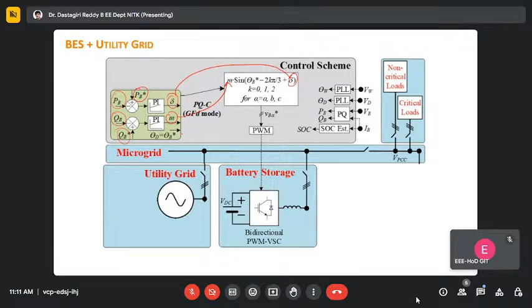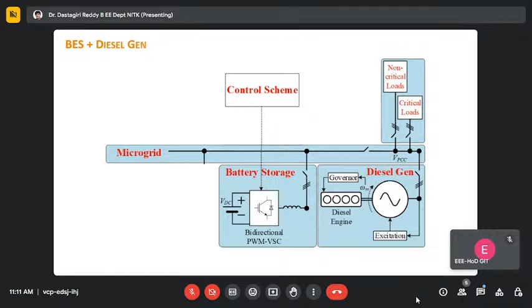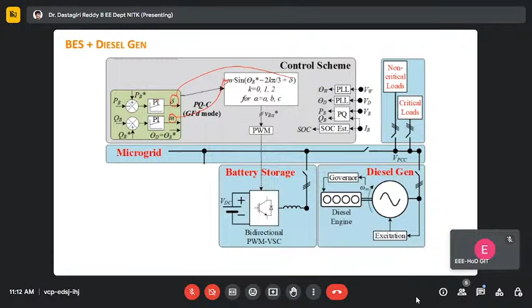So initially, what was there? Only one closed loop control, because there was only one source. Now the grid comes into picture, so I change the mode. My mode is now delta - I won't decide it myself, it will be decided by the PI controller. And the modulation index I won't decide either, it's decided by the Q control, that is reactive power control. Now if the diesel generator comes into picture, what will I do? I'll do the same thing, because the diesel will act as a strong grid and my control strategy will be the same - I update delta and update the modulation index using the same two closed loop controls.